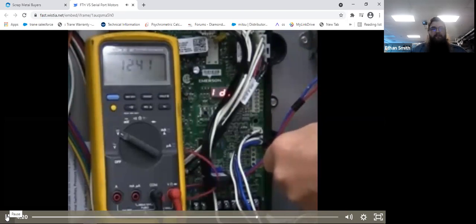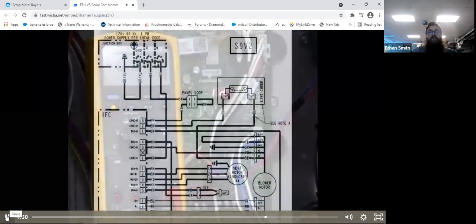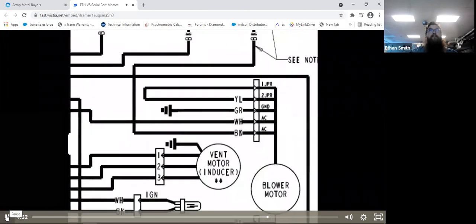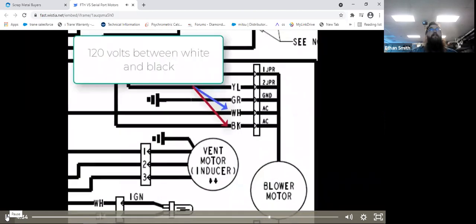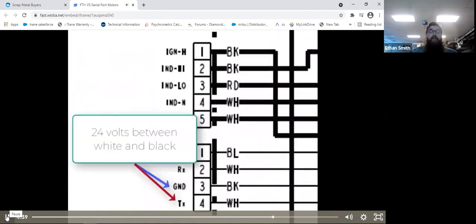But here I can see my voltage drop. And that drop of voltage is going to be at about the same pace that I see my transmit. And it confirms that my motor is sending data back to my control board. But for field diagnostics, I'm going to confirm the motor has high voltages. I'm going to apply 24 volts to the motor, and the motor should start up and run.